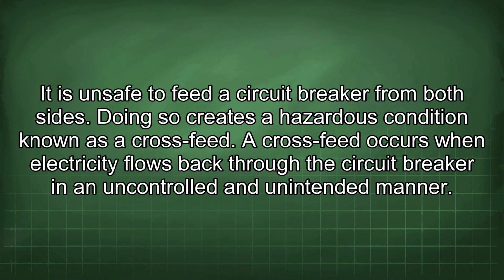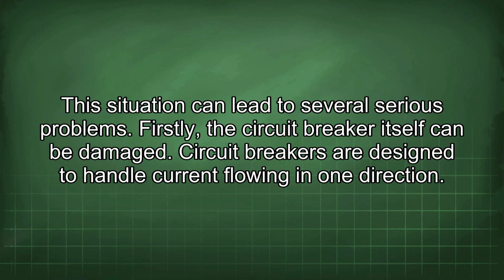It is unsafe to feed a circuit breaker from both sides. Doing so creates a hazardous condition known as a crossfeed. A crossfeed occurs when electricity flows back through the circuit breaker in an uncontrolled and unintended manner. This situation can lead to several serious problems.